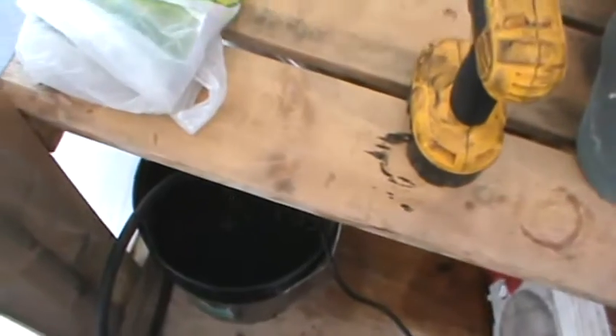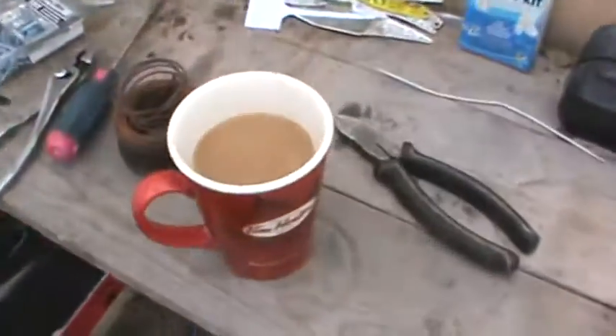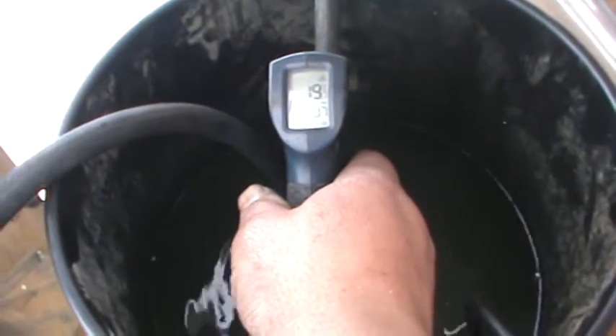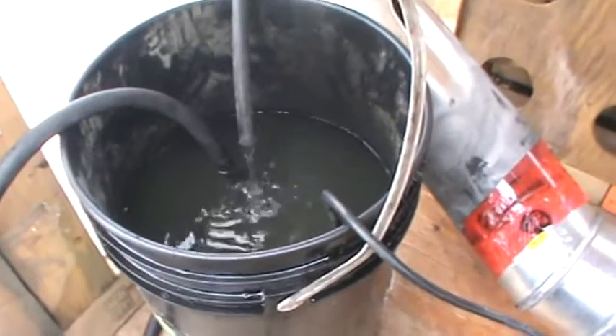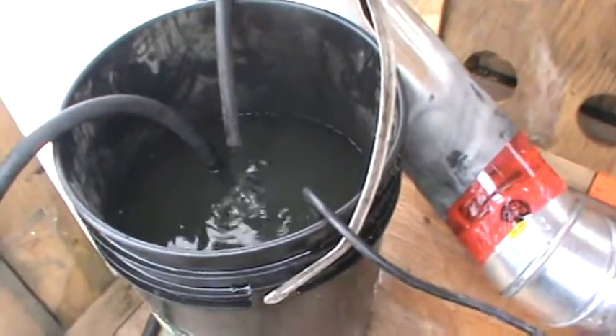Went into the house and got a coffee. When I left, the pail was at 12.5 to 13 degrees — now we're at 16.7. You'll notice the water keeps getting warmer on the pipe: we've got 20 degrees on the outlet and 15 degrees on the inlet, so about a 5-degree pickup every pass through the coil. This is only 4 gallons and it's been about 10 minutes.